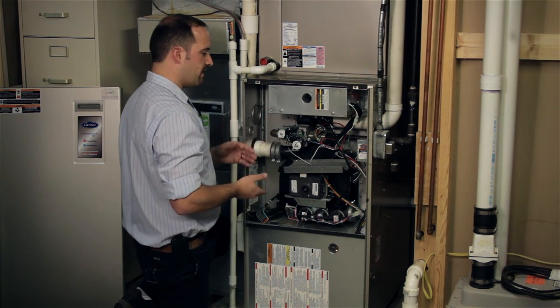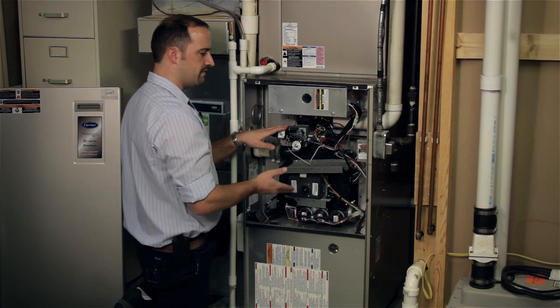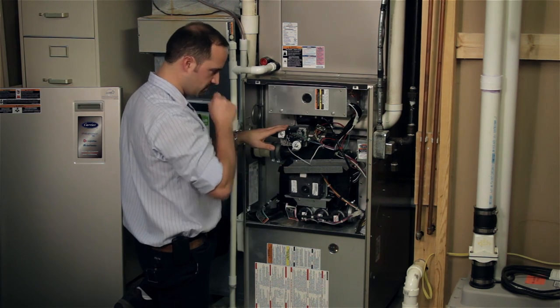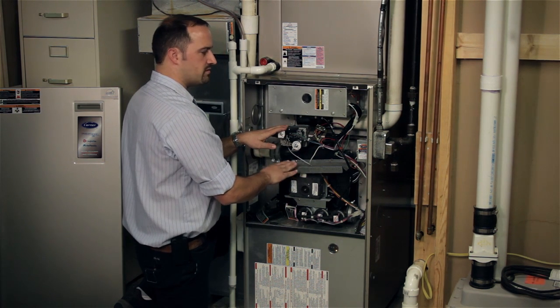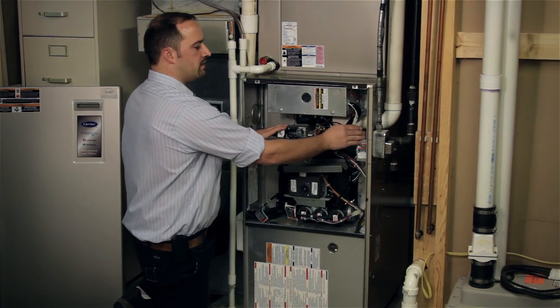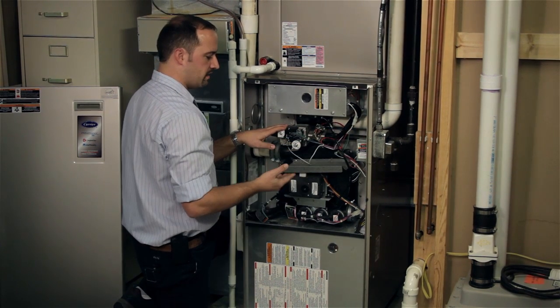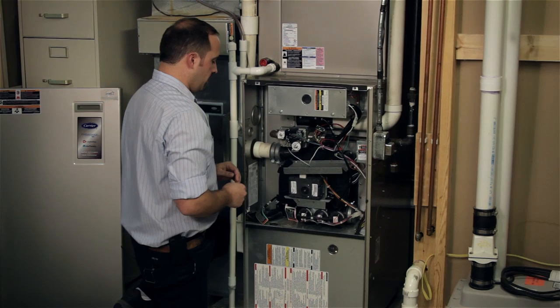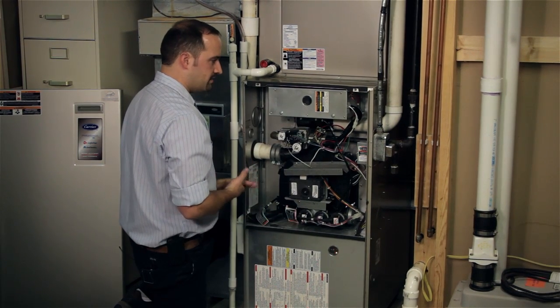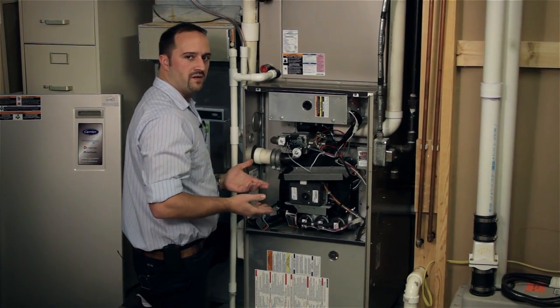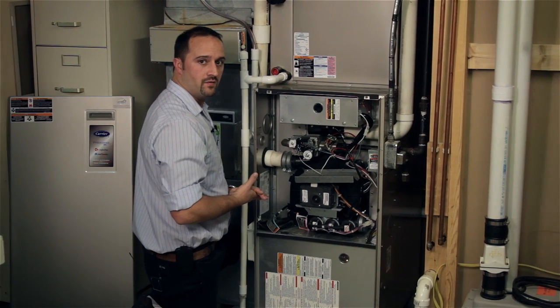Once he's checked all that out, he's going to go ahead and test the rest of the safety controls on the system. Make sure that the limit switches are operating the way they're supposed to. The ignition source for the gas is within range. He'll make sure no safeties are bypassed. And basically give an overall assessment of the condition of the furnace and everything going on.